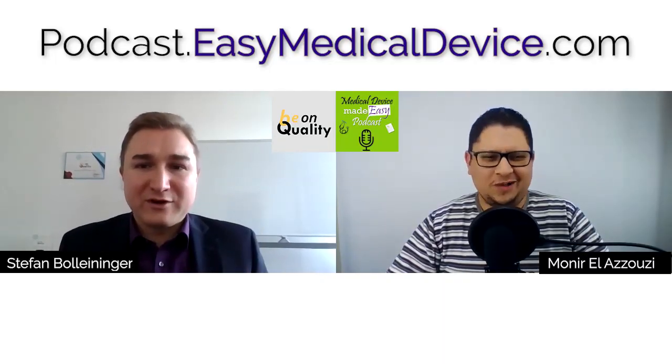So it's no rule that it must be a notified body. For ISO 13485, it can be any certification institute which is qualified according to the European law and the accreditation, and you need a notified body checking the MDR topics. It's not clever to have 2 different companies.